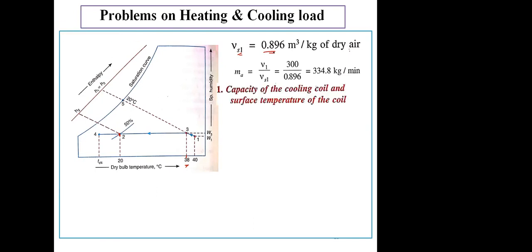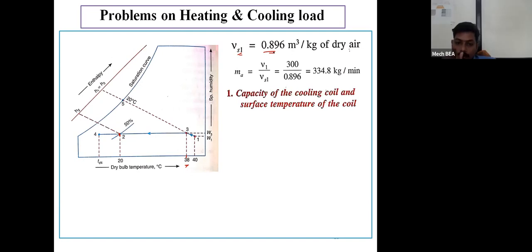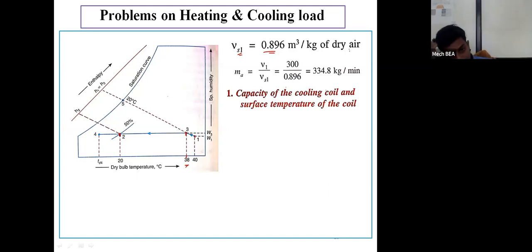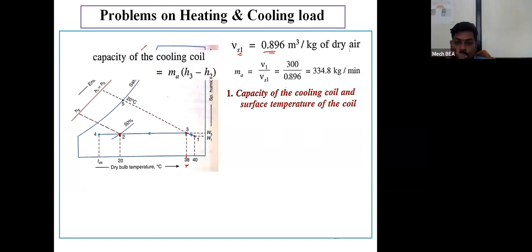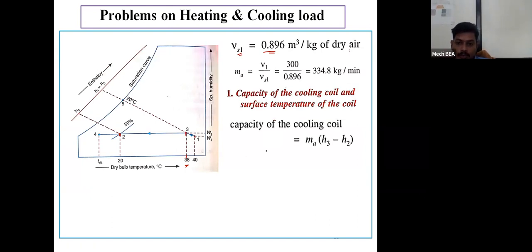Based on this, to calculate the capacity of cooling coil - here cooling coil we are using during the process 3 to 2. So capacity of cooling coil will be given by equation: mass of air into H3 minus H2.